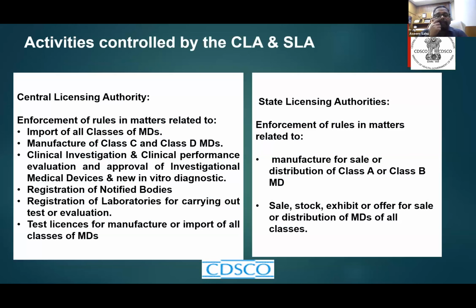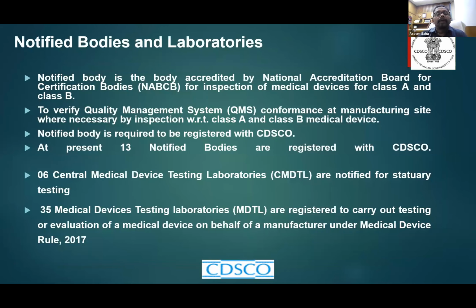This is the same repeated slide, where the responsibilities of the Central Licensing Authority as well as the State Licensing Authority as per the Medical Device Rules are given; I have just briefed here. On the role of the notified body, it has to be registered with the CDSCO. The criteria is that it has to be accredited by NABCB first, then there are certain requirements.